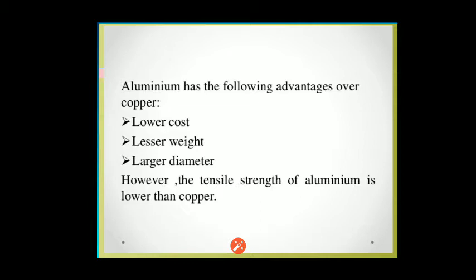Aluminium has the following advantages over copper: lowest cost, less weight, and large diameter. However, the tensile strength of the aluminium conductor is lower than copper. For the same current capacity, a copper conductor requires a 1.0 mm² cross-section, while the equivalent aluminium conductor requires 1.5 mm².